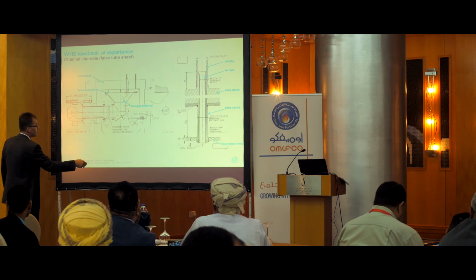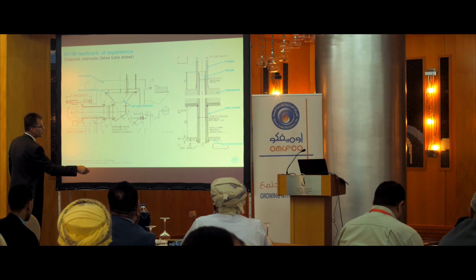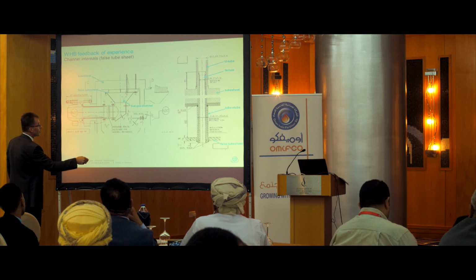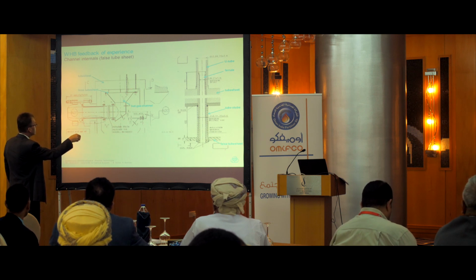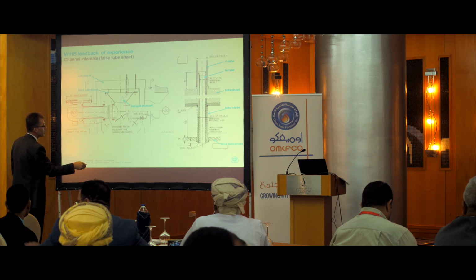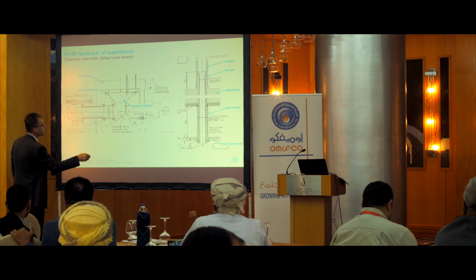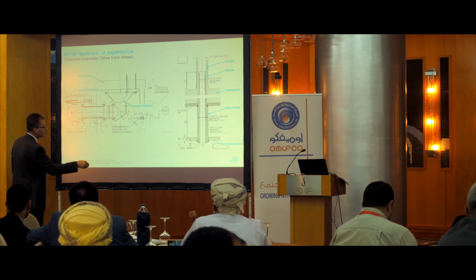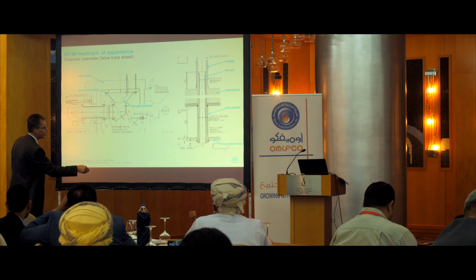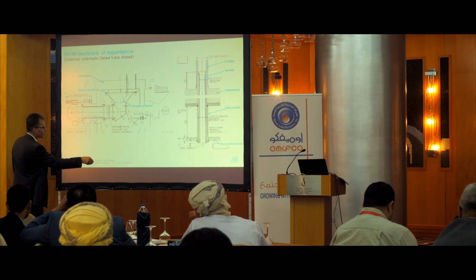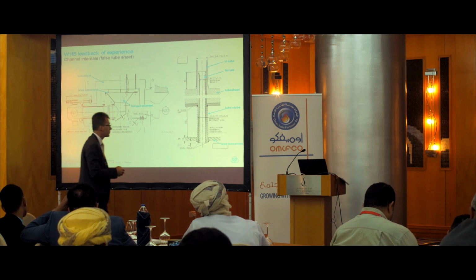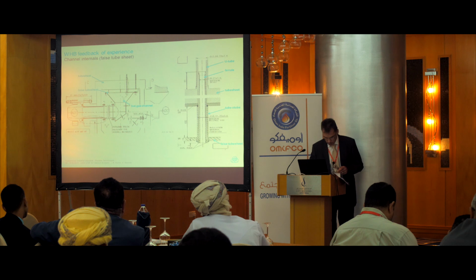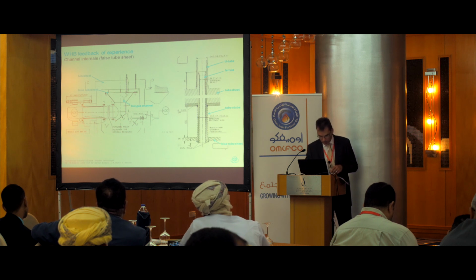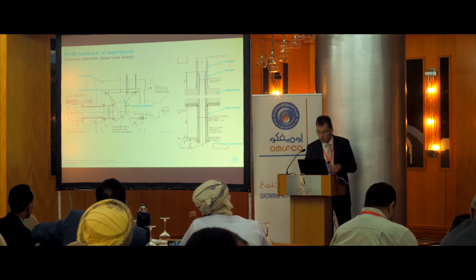Look here in this detail. This part, we call it false tube sheet. The main tube sheet is located here. It's this one here. What we have in addition, we put into the tubes so-called ferrules, also to avoid that the tube sheet will be heated up too much. And the connection between the main tube sheet and the so-called false tube sheet are tube stubs in Inconel 600. They are welded here, seal welded, so this keeps the connection from the false tube sheet to the main tube sheet. And all this is done to keep the temperature of the tube sheet well below the nitriding temperature, and in addition to cool the hot gas channel by cooled effluent gas.